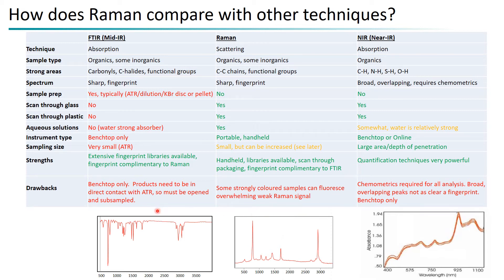The drawbacks of each technique: FTIR is almost exclusively benchtop-based, so products must be brought to the instrument, requiring direct contact with the sample — subsampling is always required, along with sample preparation such as preparing disks.